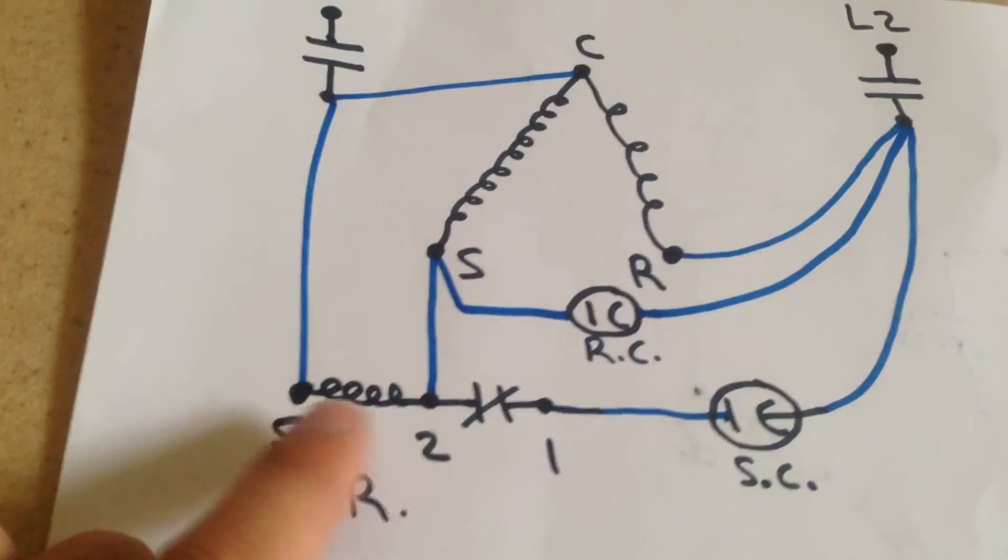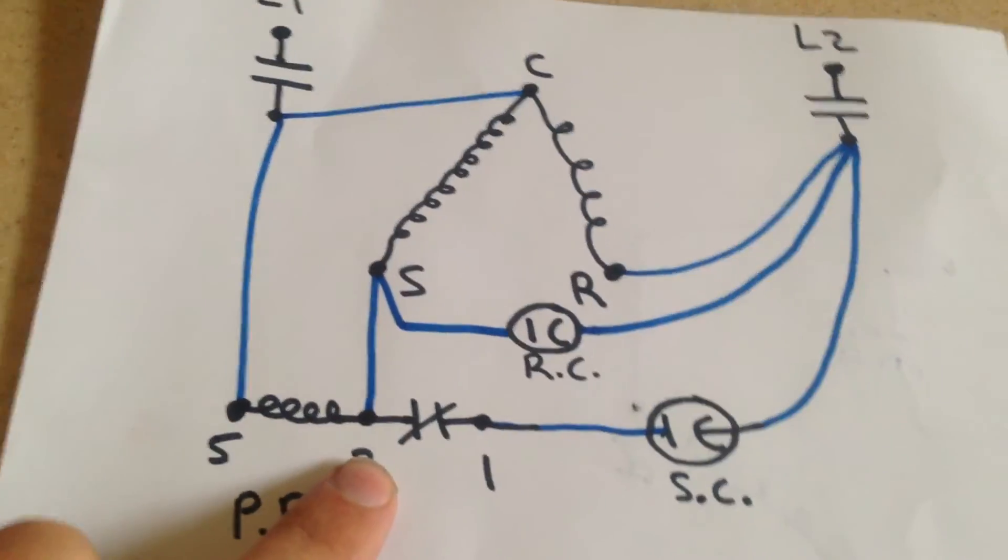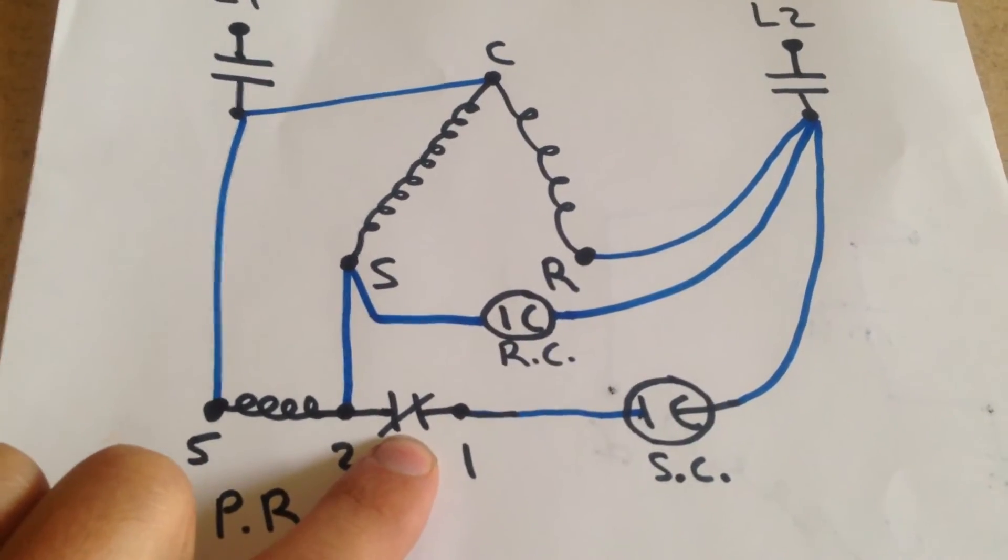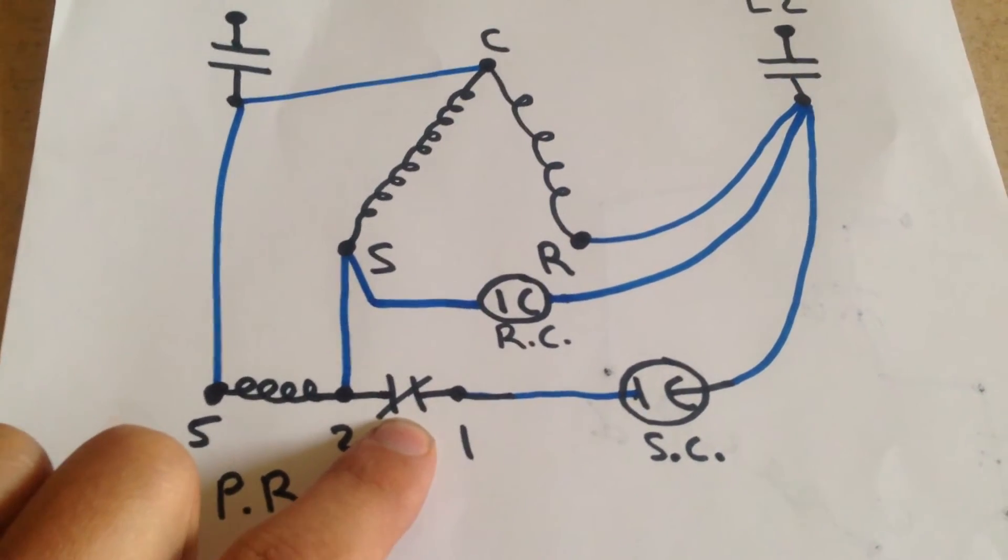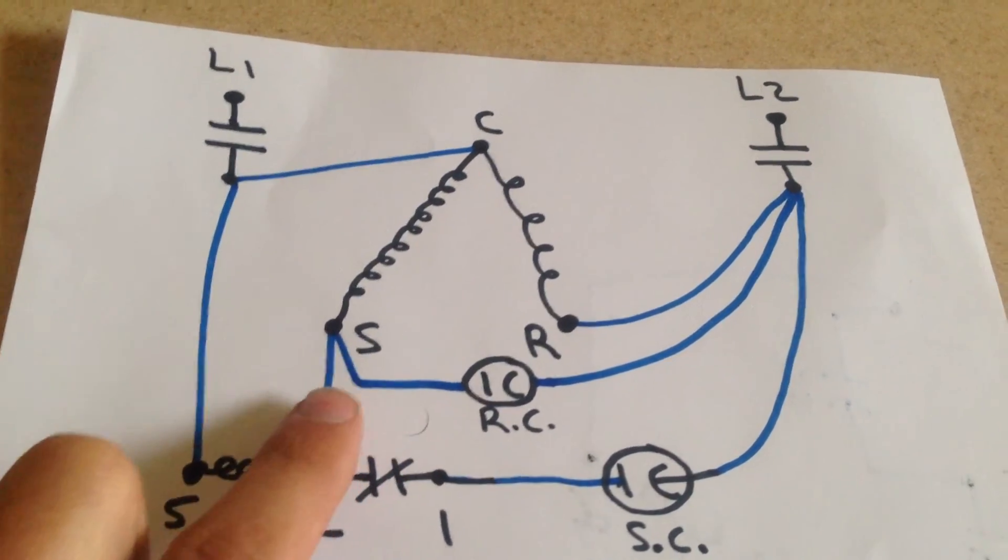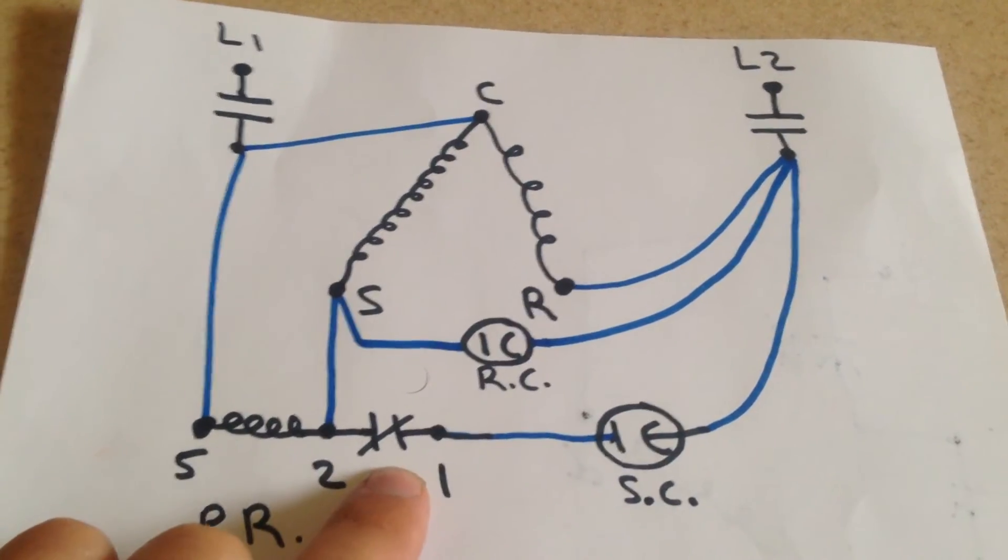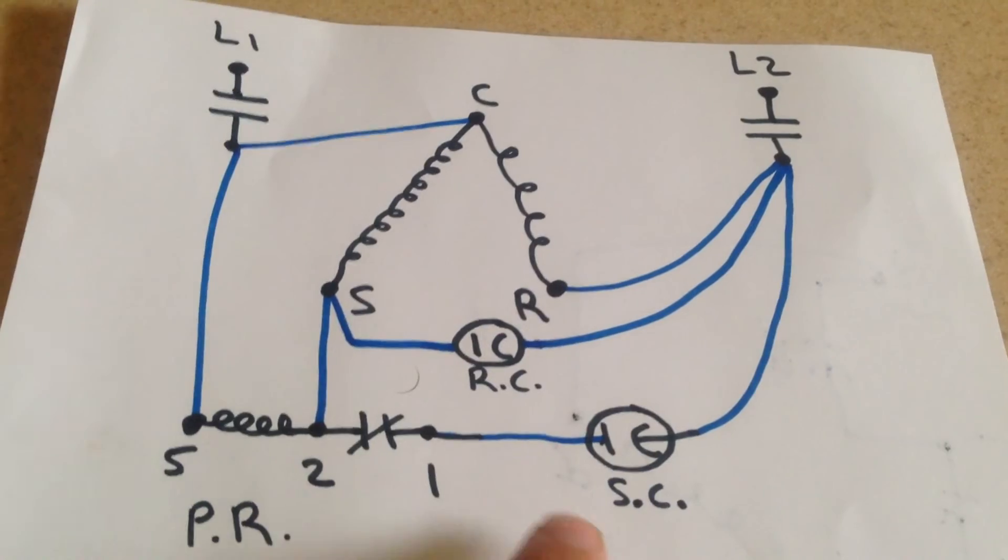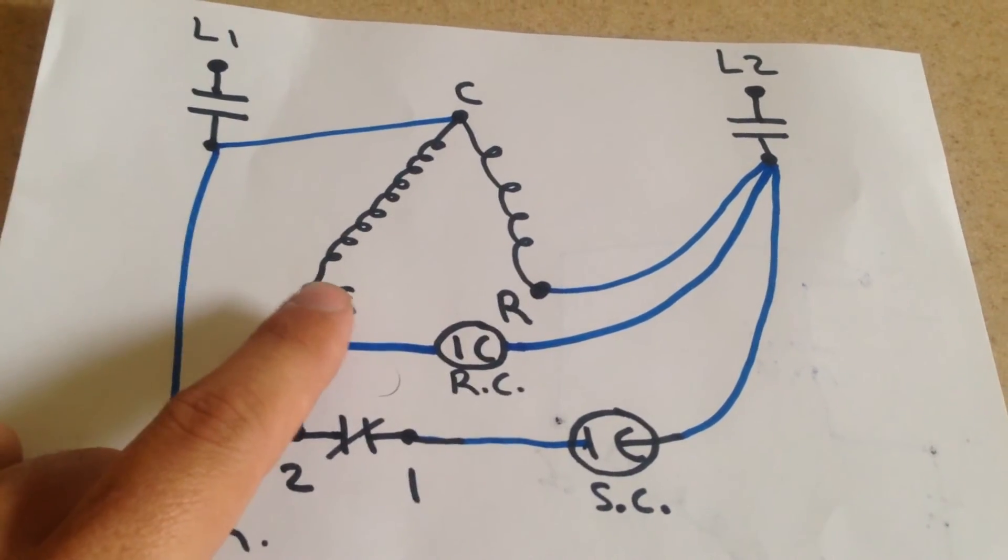So that's going to cause our coil to have enough magnetism to move our contact and change it from being closed to open once this compressor comes up to nearly full speed. So it's going to initially allow the start capacitor to help out starting the motor.